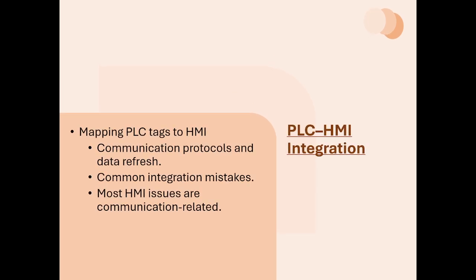Now we move into what we call the PLC and HMI integration. So the PLC, which is a computer on its own, must interact with the HMI. So let's imagine something very practical. An operator is staring at an HMI screen and sees a pump shown as running. That is, the pump is indicating that it is running, but on the field, the pump is actually stopped, it's not running. Immediately, there is going to be confusion and there will be delay and a possible risk, a hazard. So this situation usually points to a problem with the PLC and HMI integration.